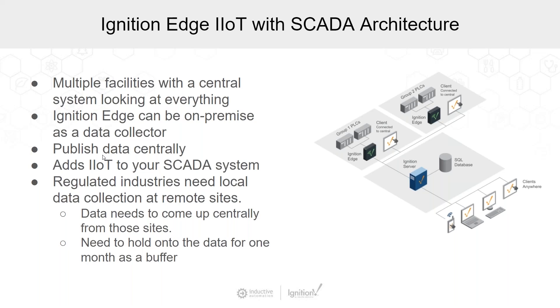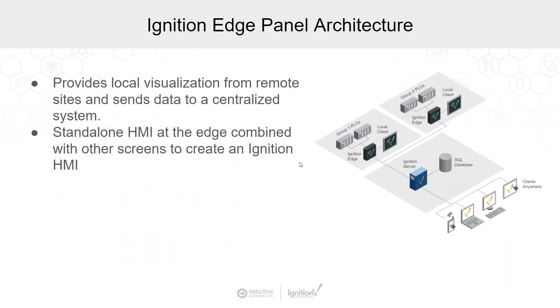We really see this as being an enabler for those kinds of architectures. It's worth noting that Ignition Edge Panel could also be used in this case, but with one difference. Instead of local clients only working if they have a connection to the central server, if I have Edge Panel, I still have local data collection and can still do store-and-forward buffering to backfill my SQL database. But now, if I lose my connection, I also still have a local client that I can use to control my PLCs. That's really the main difference — whether or not you need that local HMI independent of a central server.